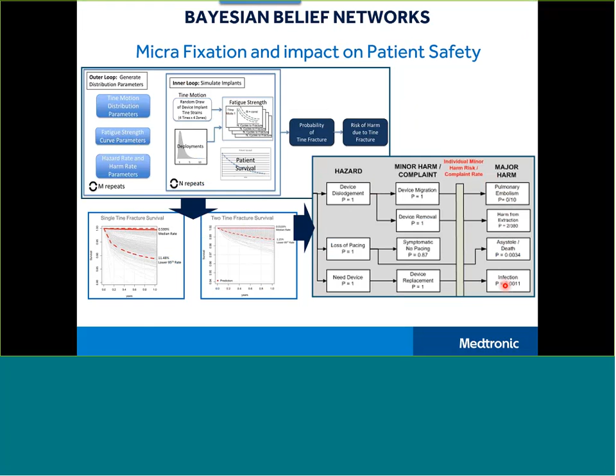And you see over here on the right-hand side, using the Bayesian network, we actually calculated the probability of problems like pulmonary embolism, harm from extraction. We calculated the probability of death for the patient, the probability of infection for the patient, and we minimized those probabilities. There was also a probability: this pacemaker that goes inside the heart actually detects the person's movement. If they're walking, if they're sleeping, if they're running, the heart needs to be paced at a different rate depending on that. And we have an accelerometer that was going inside the Micra pacemaker. And if it got stuck, it would no longer correctly detect the person's motion, and it would not appropriately pace the heart. And that would be harm to the patient as well.